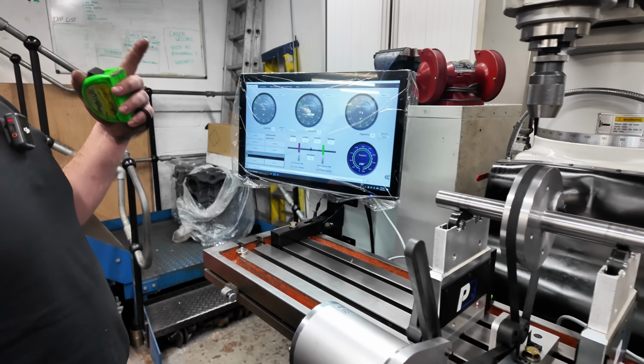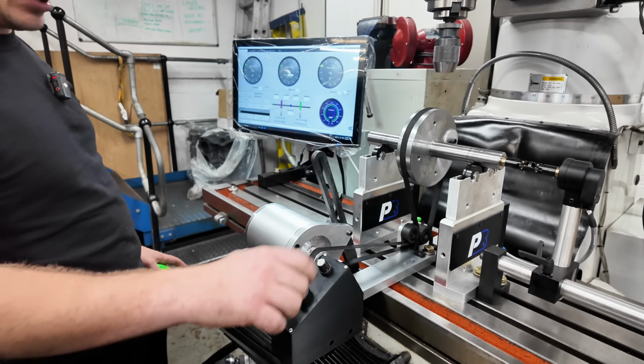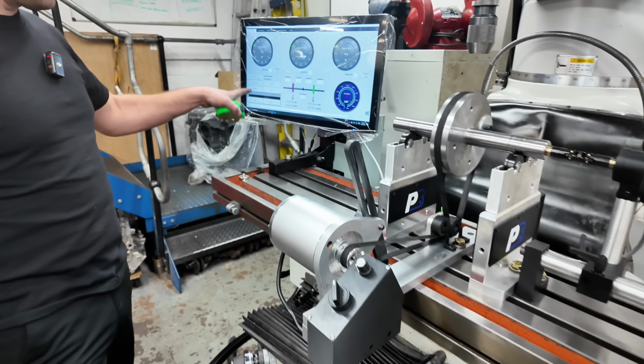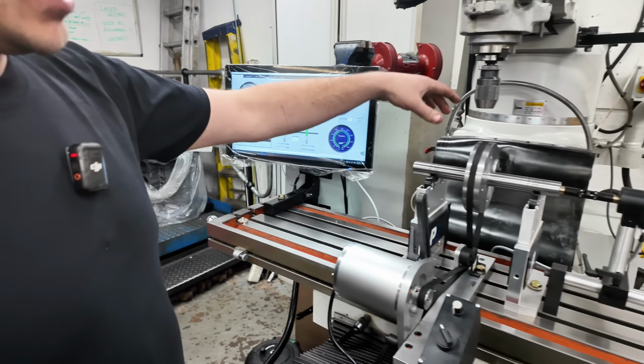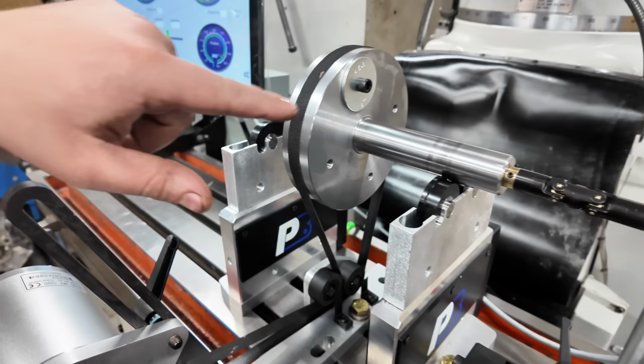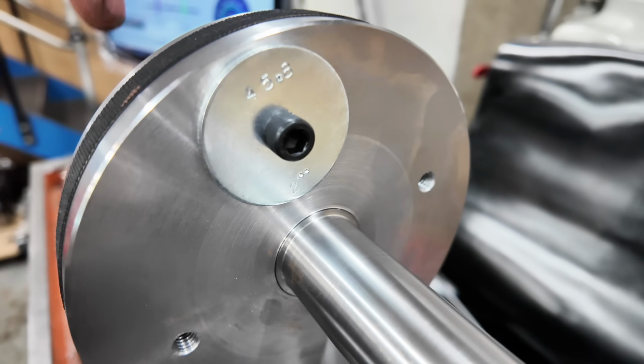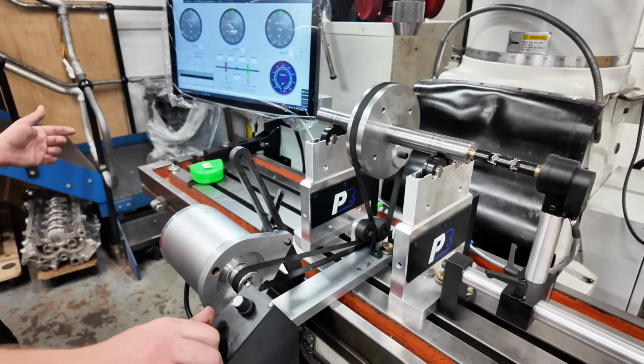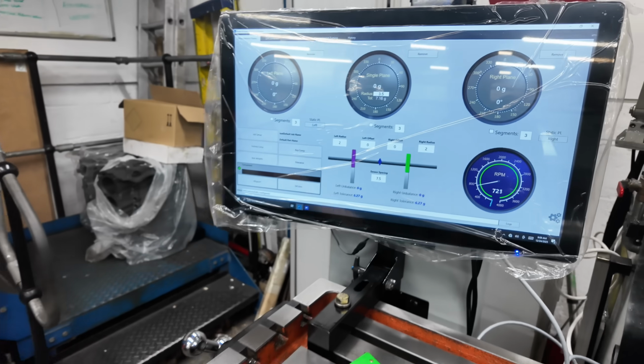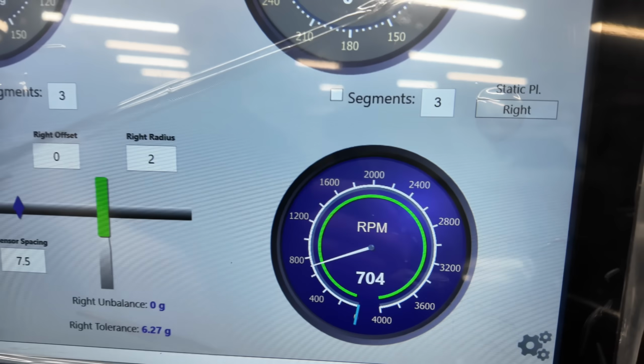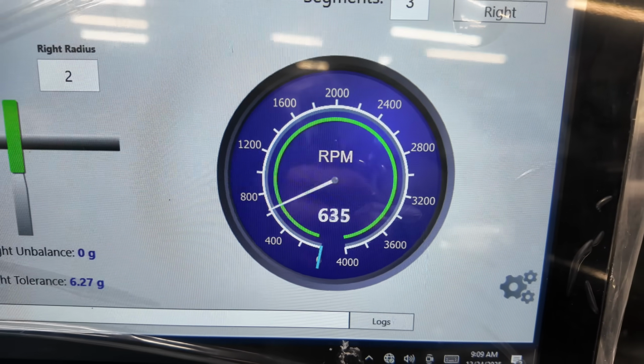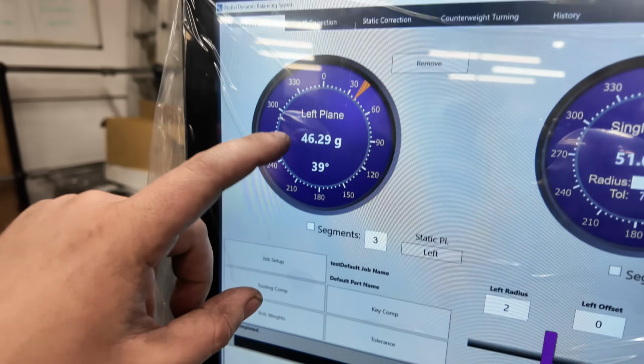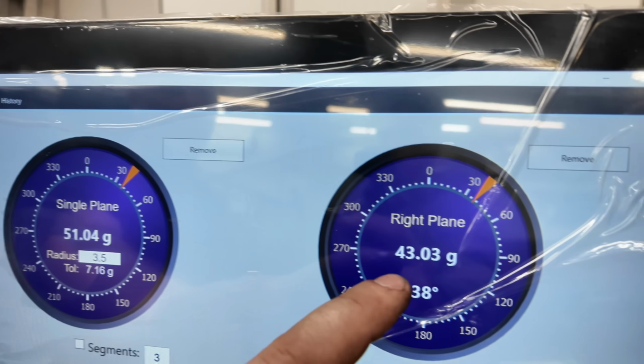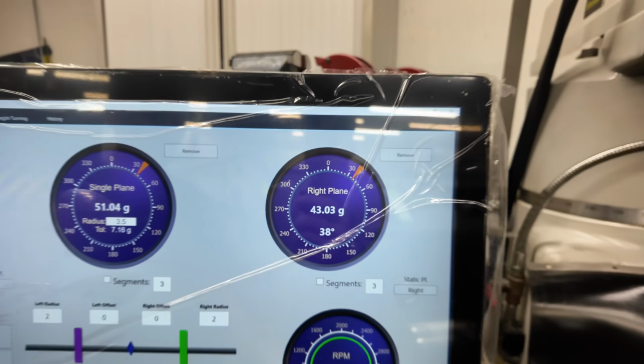That's what we're hoping. So how this all should work is this should turn it on, speed control here, and then we can click measure. Now, if you guys look, because this is a calibration unit, you have the ability to bolt weights in. So what we're going to be doing is we should see some imbalance. So if we now switch that on, you can see here, we've got a clear RPM reading. And we can speed that up and change that. And look, the machine is automatically gone to measure, and we're seeing 46.29 and 43.03 grams of imbalance.